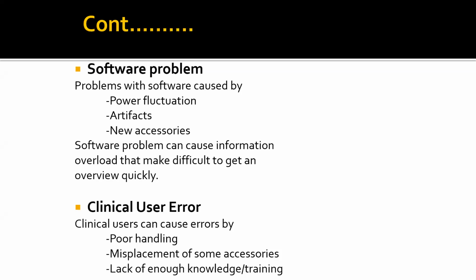Then clinical user error is basically lack of knowledge and poor handling. They drag the patient monitor by the probe cable instead of carrying the patient monitor. I've seen a few places doing this. So for awareness of the clinical users, you as biomed have to give awareness or training on the proper way of using it, to make sure the probe lasts longer and the patient monitor works properly. This is one of the things that you need to do.